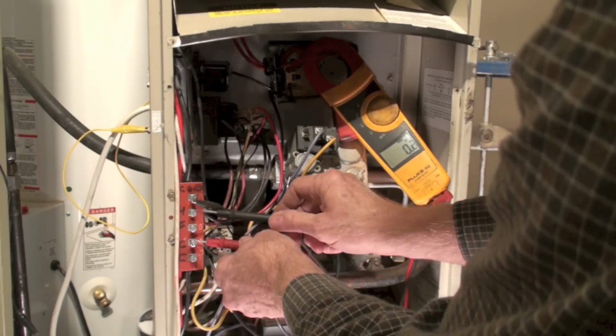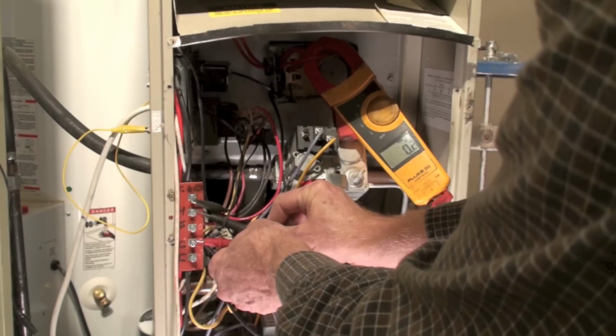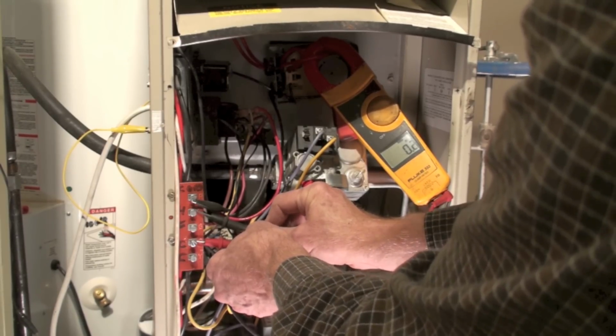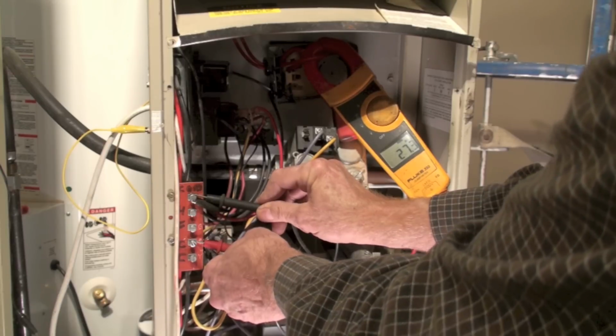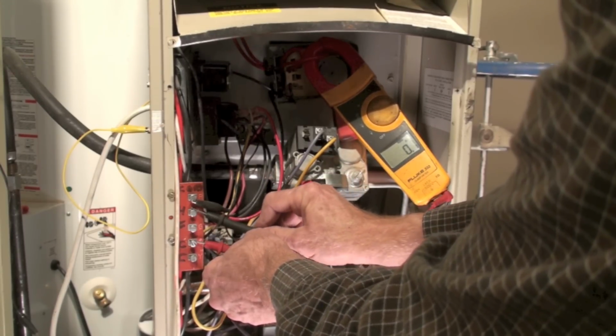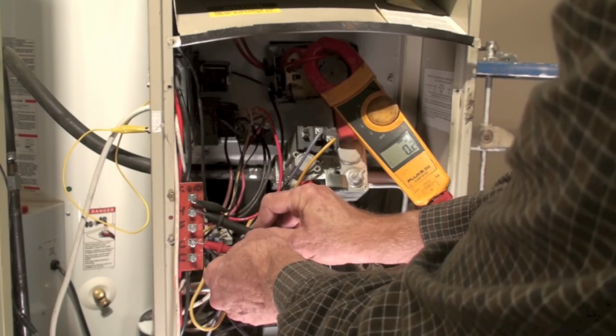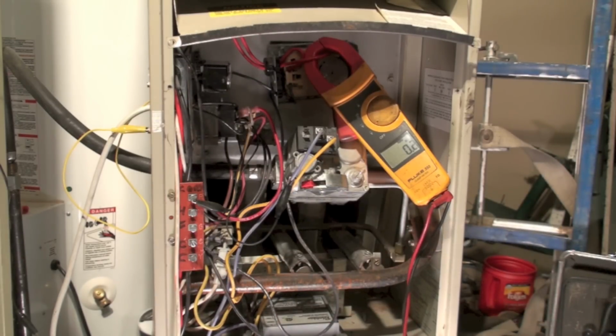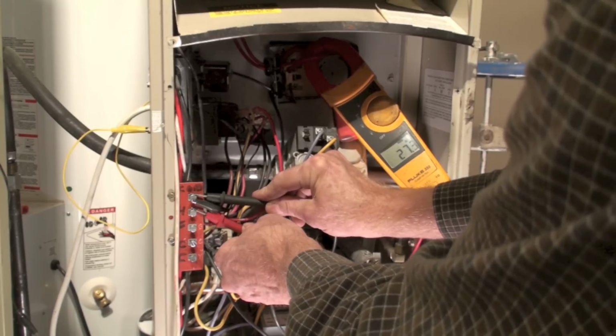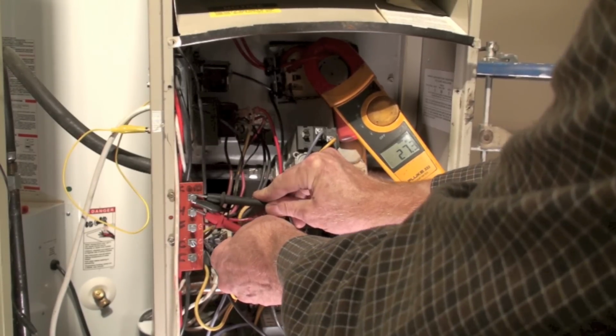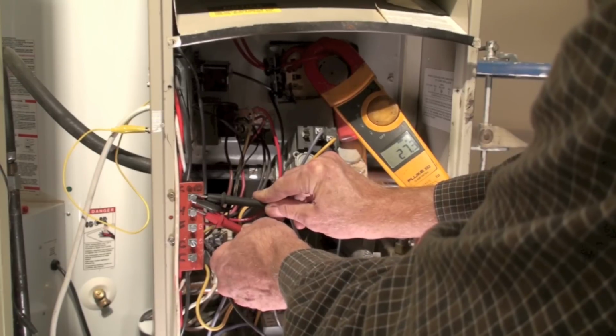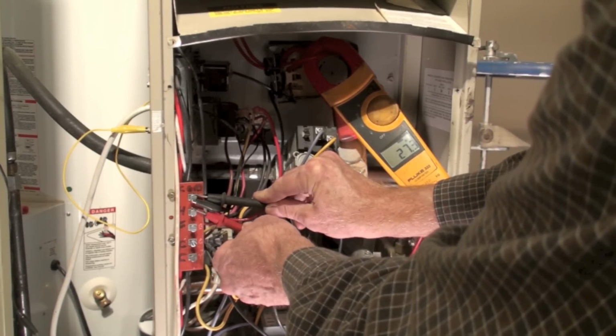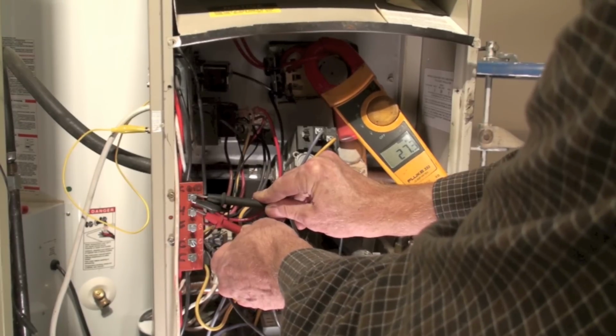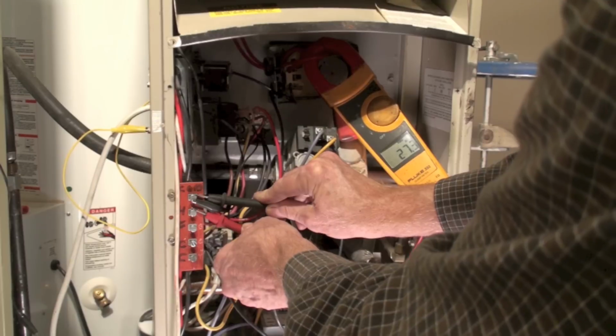Now, in this case, it did show nothing at all. I have eliminated the furnace as being the problem at this point. If I had power between C and R, as I do, but no power between C and W, then I have a problem in the thermostat. Now, to make sure, just as a double check, go between R and W. Now, I should read voltage there. That may seem a little odd. However, if the thermostat is open, that means there's no continuity through it, then I'm going to read 24 volts. In this case, 27, but whatever. So it is a thermostat problem.